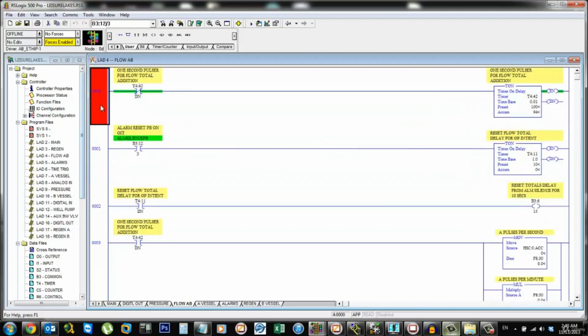But it's very important to understand that each one of these rungs runs from left to right. And why that's critical is because this giant gap here in the middle, all this white space on our rungs, divides our conditions on the left from our outputs, or you might think of them as actions, on the right. So imagine this program is running right now and it's scanning, and we're going to go step by step how the PLC is going to scan this program.